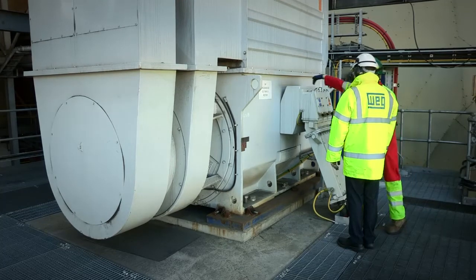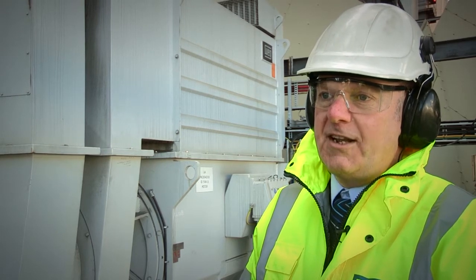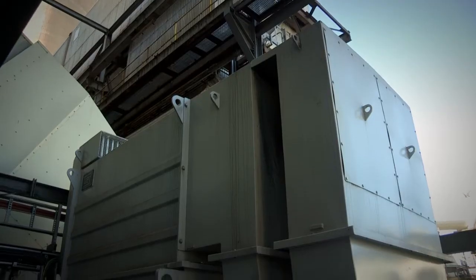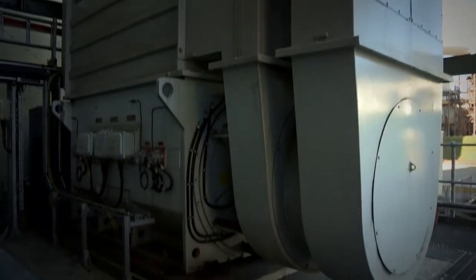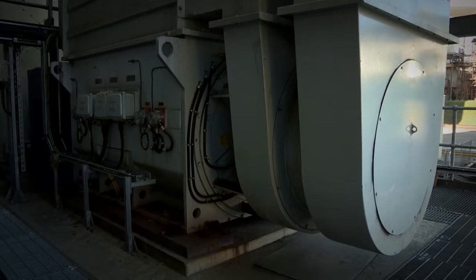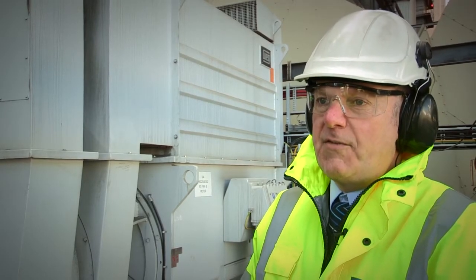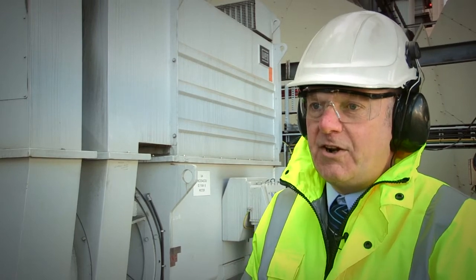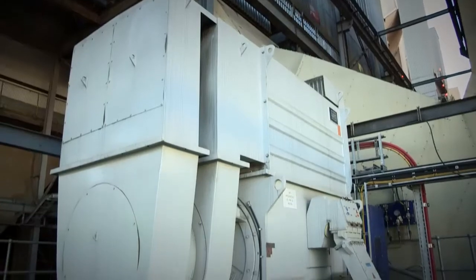This project's been going on for four years now. Motors were ordered back in 2010 and have been installed periodically over that time, two at a time. The last two motors are due to go in May of this year. There are eight 4.3 megawatt machines, 6.3 kV, and they're all driven by variable speed drives, which have a speed range of 30 to 100% full speed.